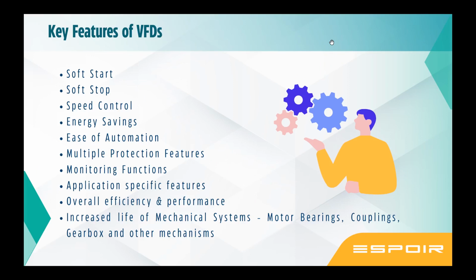Then there are application-specific features. For example, if you have a lift, there are lift-specific parameters. If you have a crane application, there are crane application parameters. You have a compressor, you have a pump, any application, there is a set of application-specific parameters. Then it also helps bring overall efficiency and performance to a system. Now, having a soft start and soft stop increases the life of the components connected along with the motor, which are the motor bearing, the coupling, the gearbox, and other linear mechanisms connected on the same shaft of the motor.